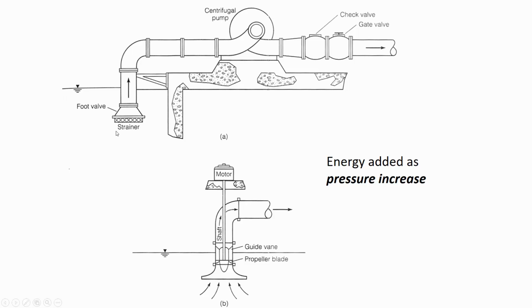Now the water is going to go into the suction side of the pump. This strainer keeps branches and leaves and baseballs out of the pump. But then the water is traveling through the suction side. What happens to pressure in a pipe in the direction of flow?